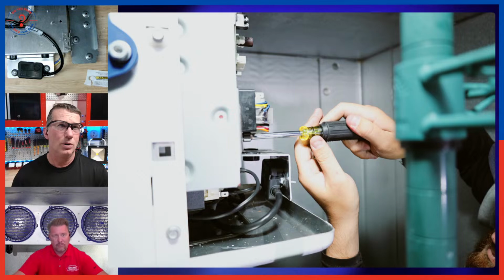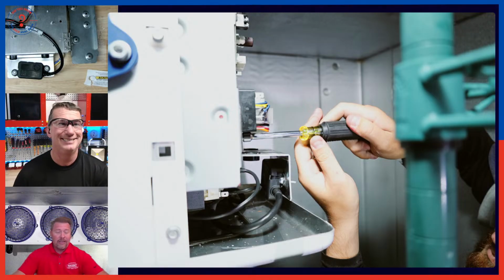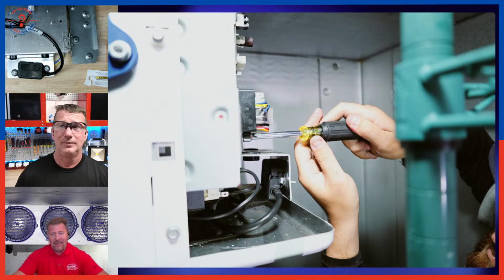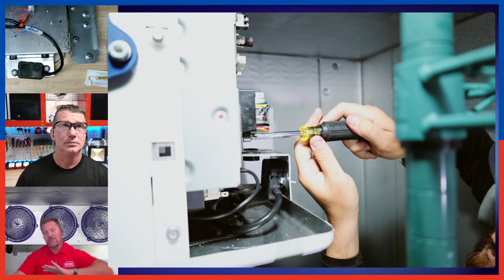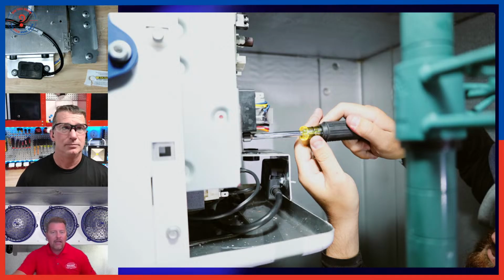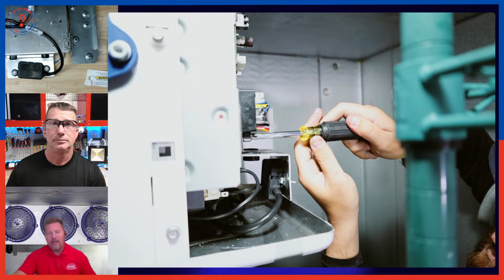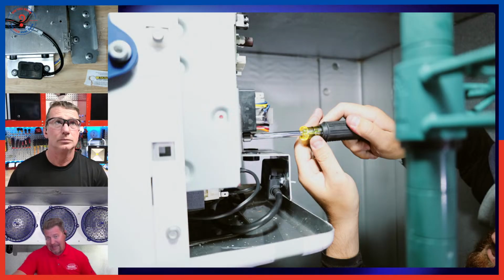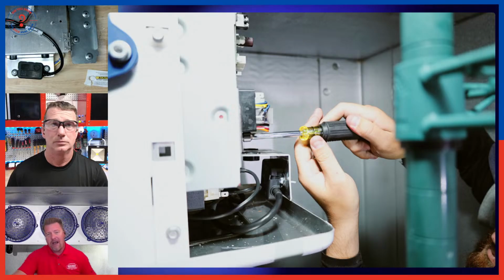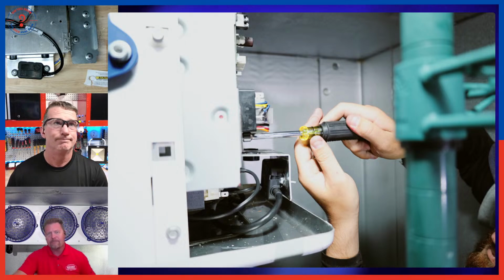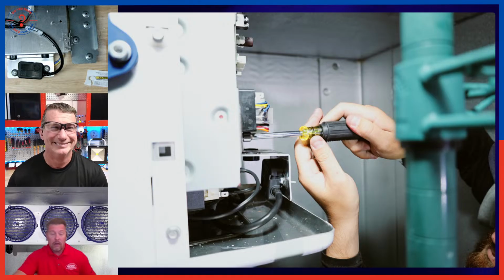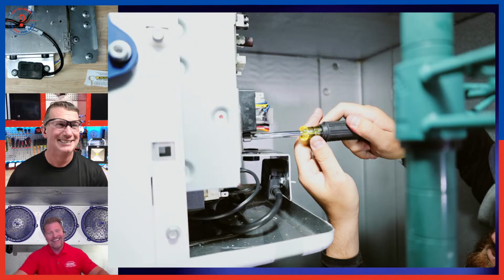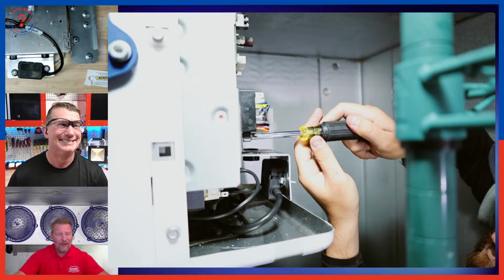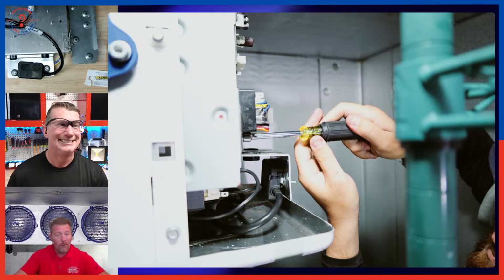Because I've had that question before: well, what happens when we start building up ice on the return bends? Well, we have a cover. You're quite a ways from it, and again, this is on the electrical side of the unit. Your distribution tubes are on the other side. So, not to say it could never happen, but chances are that long before the ice got to that sensor, the box would already be warm, or somebody would notice and hopefully call their technician and say, hey, I've got 3 inches of ice on this coil, and my walk-in's 50 degrees. Yeah. Hopefully your client or your end user notices the temperature is warm long before ice builds to that sensor.